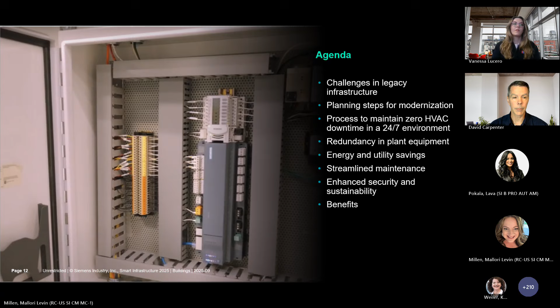One of the challenges we frequently see, not just on this site but many others, is old wiring or old labeling. A lot of the panels have undocumented wire changes that happened through the years, or the handwritten wire tags have worn off, so it's not trustworthy for a replacement.